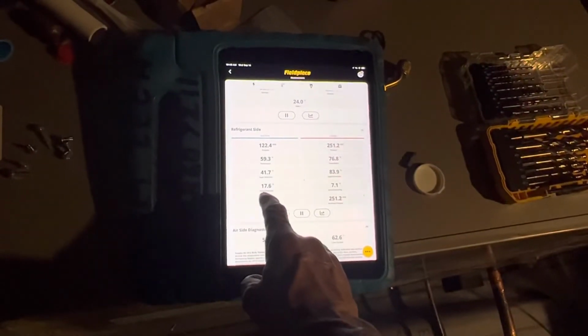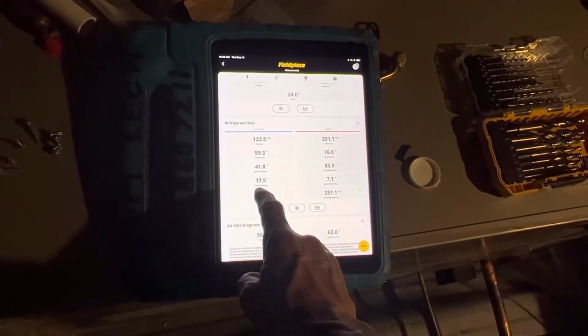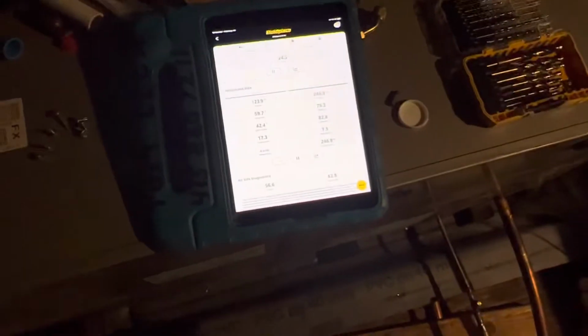I cannot take account for the superheat they have, I cannot do that right now because you need to have your guy put on the insulation on the suction line, because right now it's absorbing heat from here in the attic and all along. So it messes up my readings out there, because by the time the gas, this is a returning gas, returns from this point back to that point, it has changed temperature and it throws off the readings. So I can't check that.